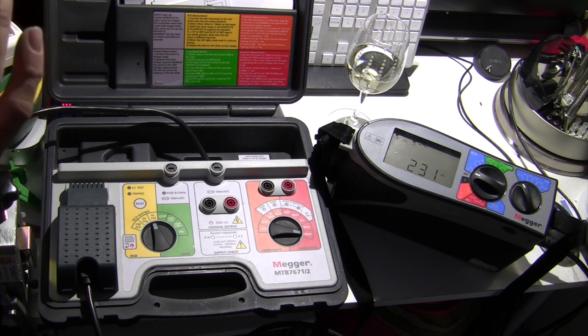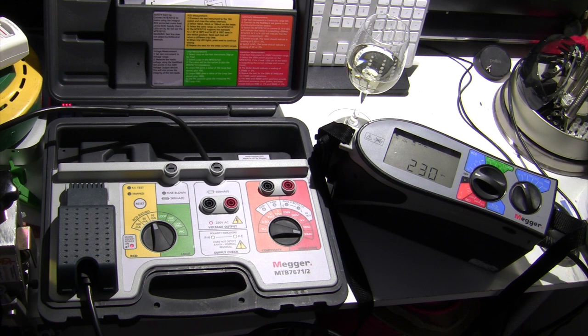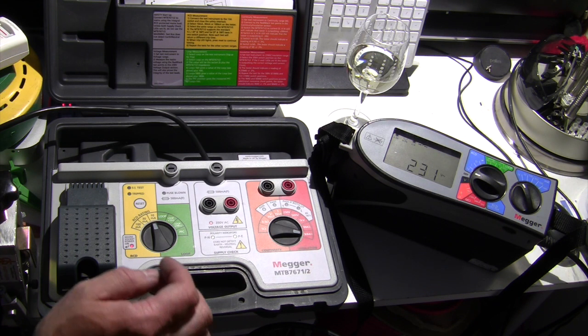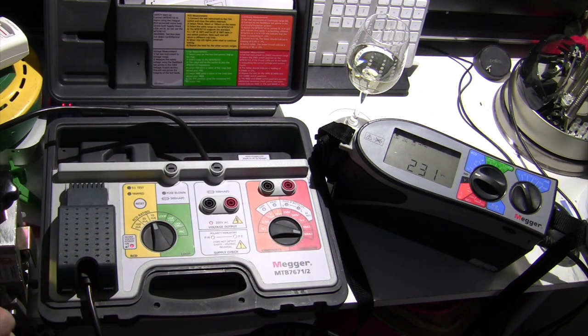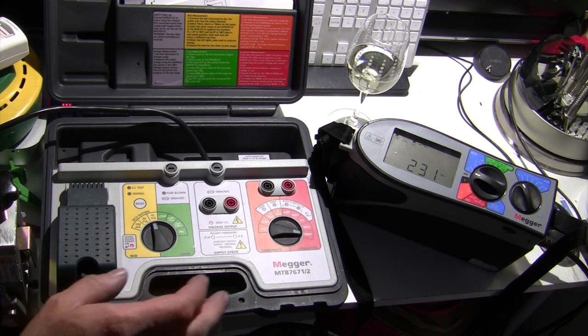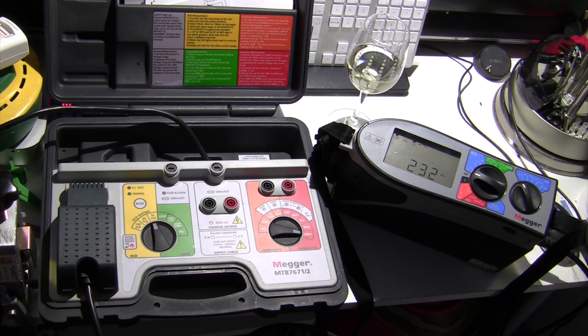Now although this has an auto test, I'm going to go through the test manually just because the auto test is a bit fast, and I'm going to take it slow. We're going to do the 5 RCD tests to see if the numbers that come back are the numbers we expect to see. Now I should say that this is plugged in to an RCD protected circuit. There's an RCD back at the board of the circuit that this is plugged into. However, this is simulating an RCD, so it's not going to trouble the board, even though I'm sending a fault current to earth effectively to test the RCD.